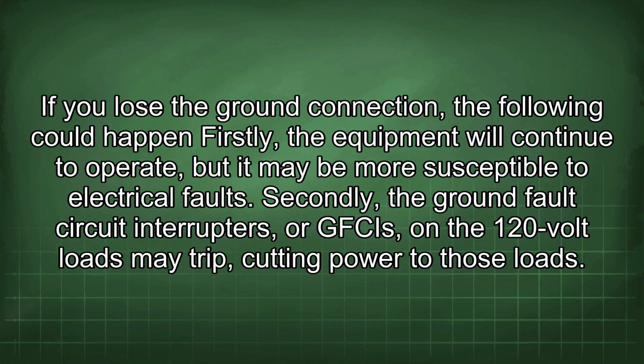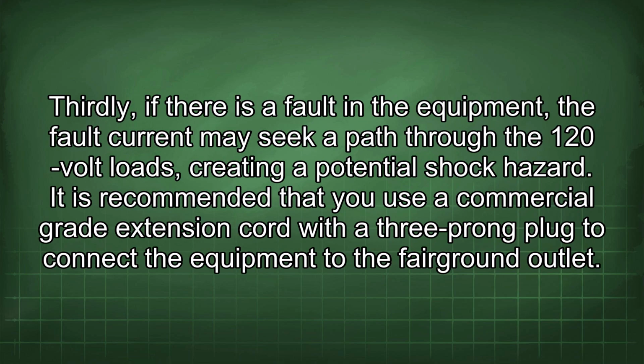If you lose the ground connection, the following could happen. Firstly, the equipment will continue to operate, but it may be more susceptible to electrical faults. Secondly, the ground fault circuit interrupters, or GFCIs, on the 120-volt loads may trip, cutting power to those loads. Thirdly, if there is a fault in the equipment, the fault current may seek a path through the 120-volt loads, creating a potential shock hazard.